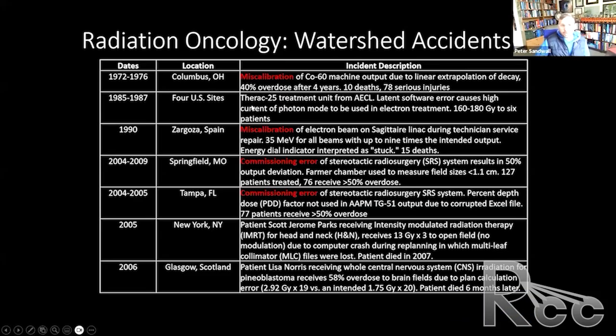I think many of us have heard about Therac. This was a software error, and this was also fatal to people. There was a miscalibration in Spain on a Sagittaire Linac. Again, this led to deaths. This is a serious event. Springfield, Missouri, a commissioning error. They used the wrong field size factors. They used a Farmer chamber, so this was not fully in the treatment beam. So they miscalibrated it. And again, this led to significant overdoses.